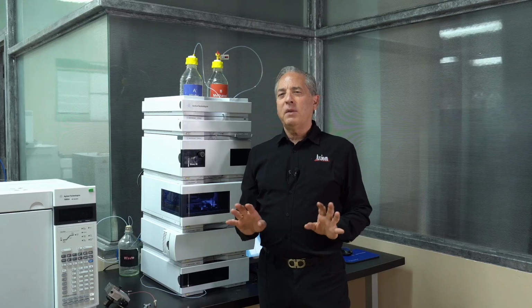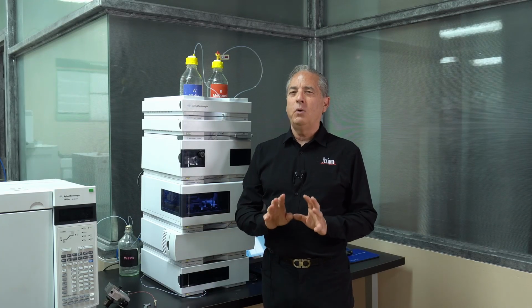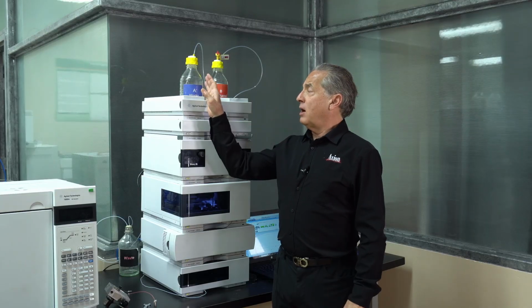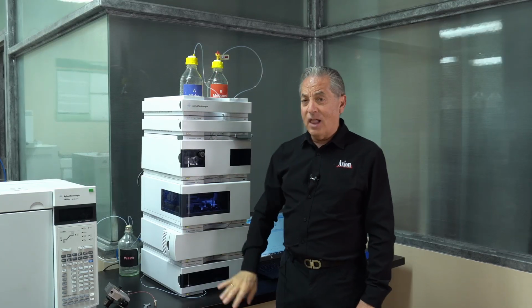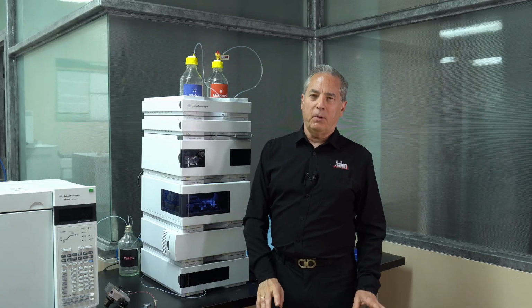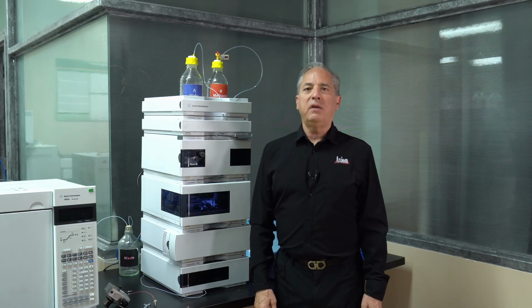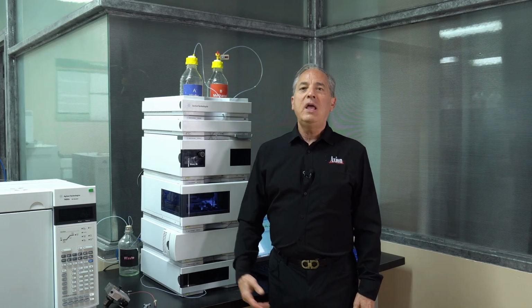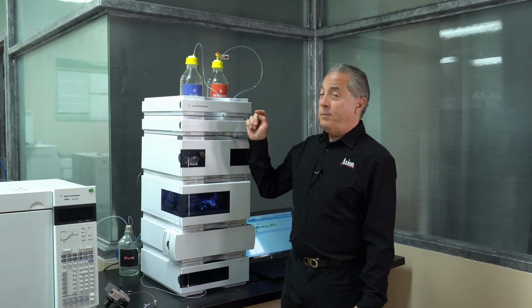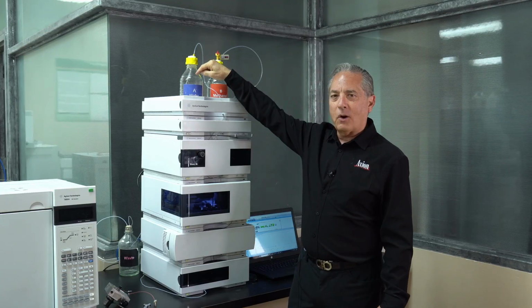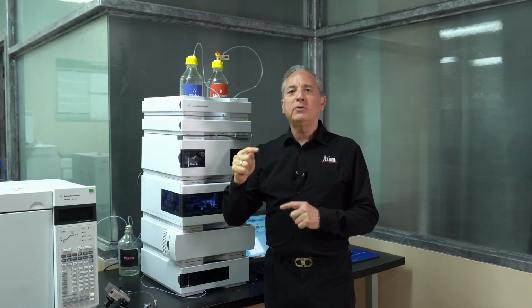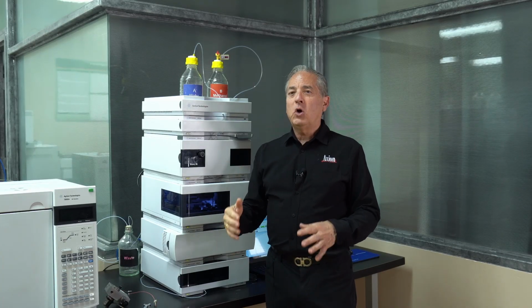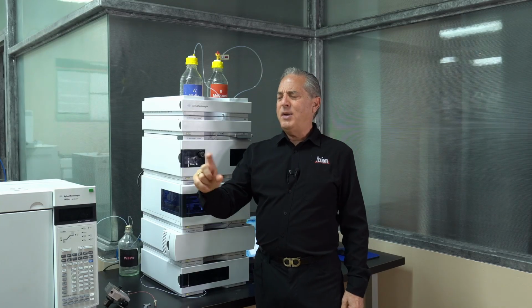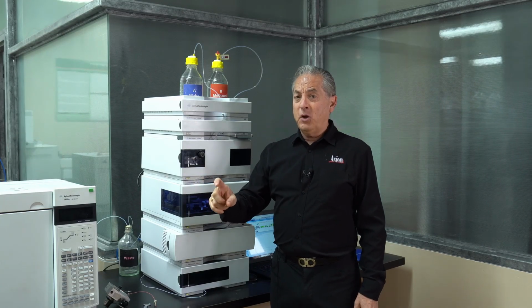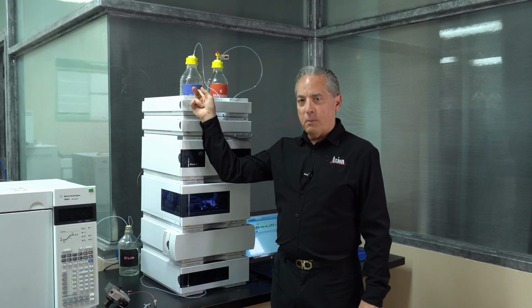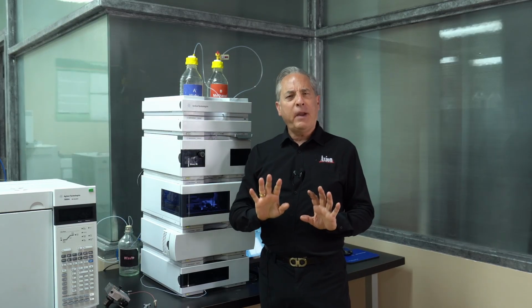Now, if it sounds like I'm being really paranoid about the water bottle, I am, and let me explain why. If you get an impurity in your water bottle, the mobile phase on the column, you put about 1,000 times more mobile phase than sample. If you make a 10 microliter injection, and if you run 10 mils of mobile phase for equilibration, then that's 1,000 times different, which means a 1 ppm impurity. If you had naphthalene, a 1 ppm impurity in your water bottle, it would show up in every sample as a 1,000 ppm impurity, a gigantic peak in every sample. So when people are chasing little impurities, they say, I have this peak, it looks about 20 ppm. It could be an impurity that's 20 parts per billion in their water bottle. There's this concentration effect. So be paranoid about your water bottle.